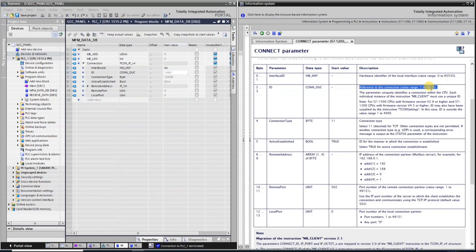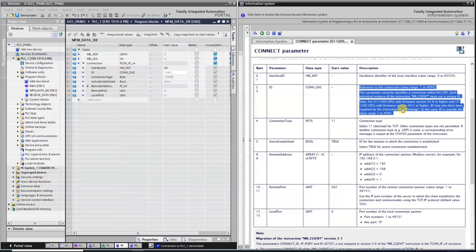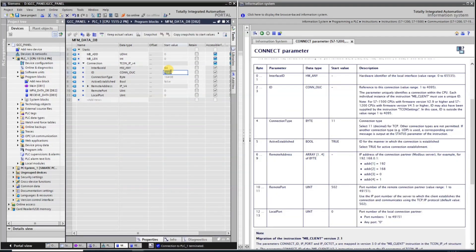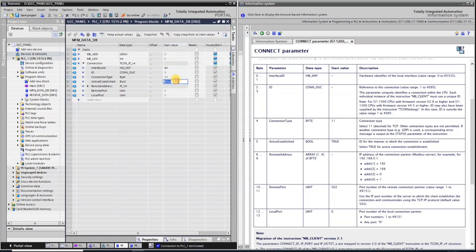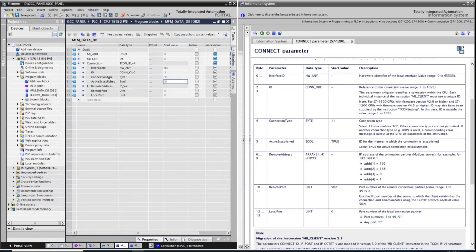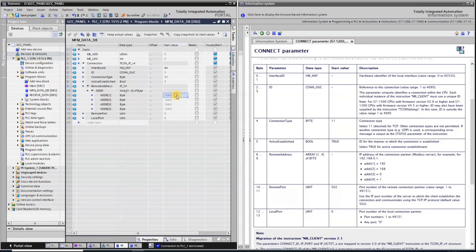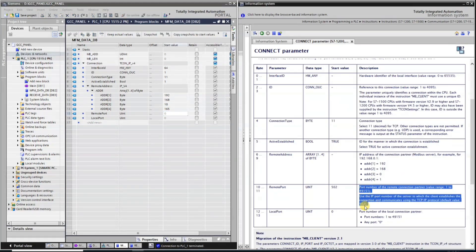Here I take an ID number of 1. The next parameter is connection type. The connection type parameter in a client communication block defines the communication protocol to be used for network communication. The numeric value you enter depends on the protocol you are using. Normally we use 11, 17, 19, or 16, which depends on our communication type.